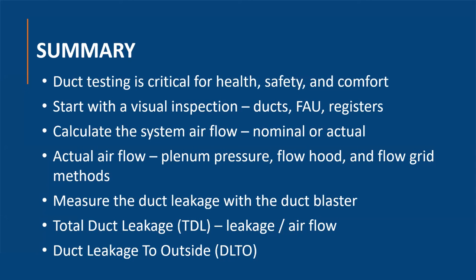In summary, it's important to remember that duct testing and duct sealing provide more than just energy savings and comfort — it's critical for indoor air quality, health, and safety as well. Start with a visual inspection of all the ducts, the forced air unit, and registers. Calculate the system airflow using nominal or measured system airflow, with actual airflow measured using plenum pressure, flow hood, or flow grid methods. Set up the house correctly and measure the duct leakage with a duct blaster — you can measure total duct leakage or bring in a blower door and measure duct leakage to outside. Both tests provide detailed insight into the condition of the duct system, but be sure you know if one or the other is required for the type of compliance testing you're reporting for, and always use the same method at test-in and test-out.